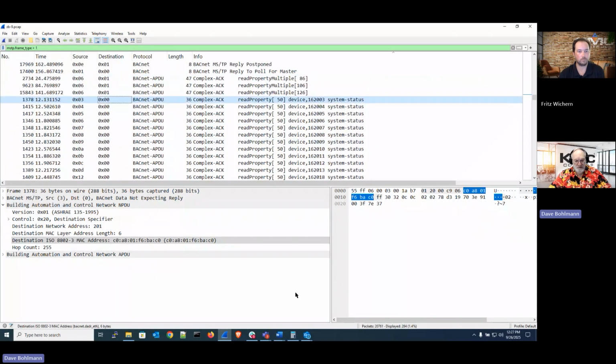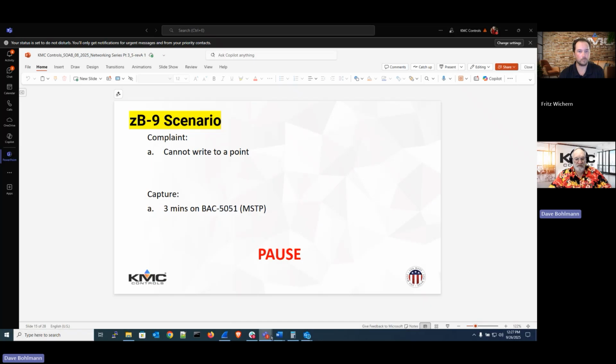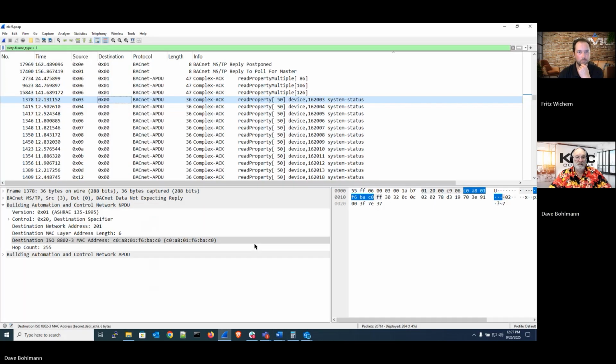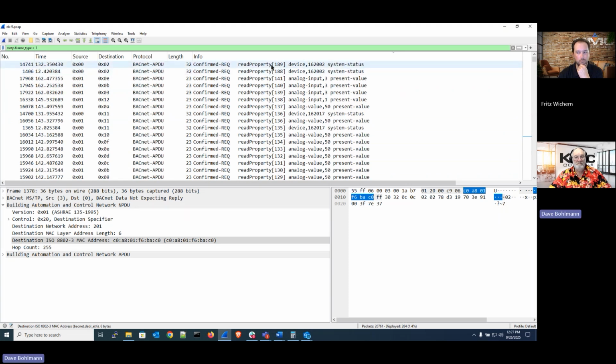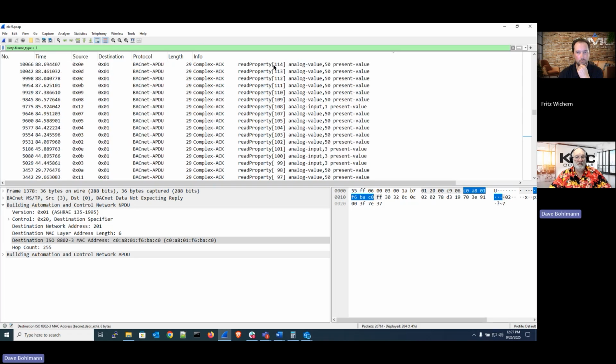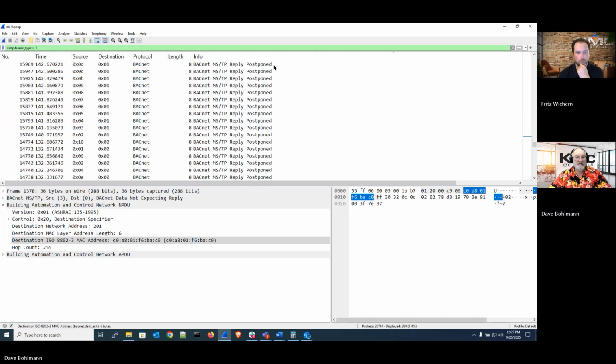But what was the complaint here again? It was cannot write to a point. So let's focus on that. And so now we can filter on here and try to see if we can find the write. There's not that many messages. We can just scroll through here and holler if you see the word write property. Postponed, say we get rid of that. So I did not see any writes in here.